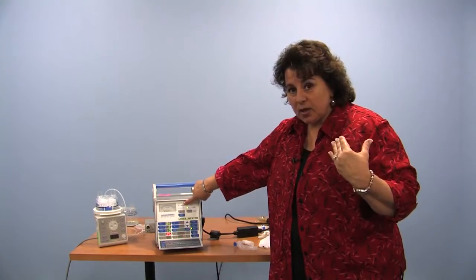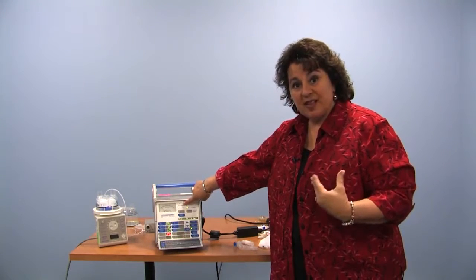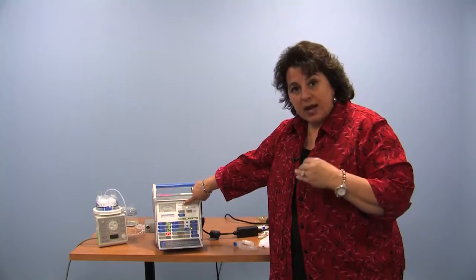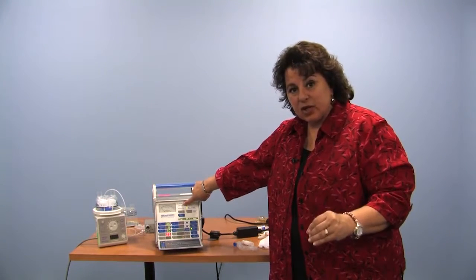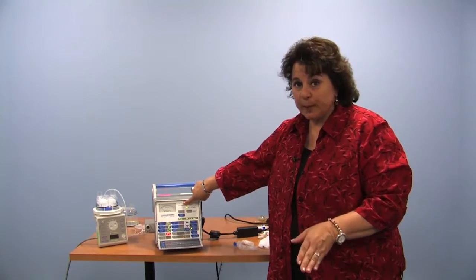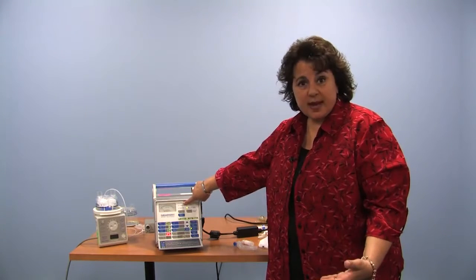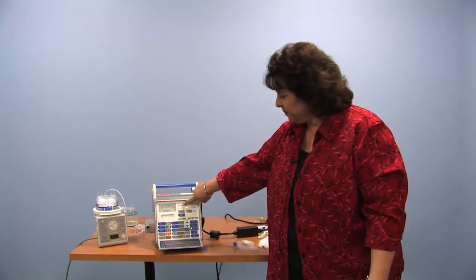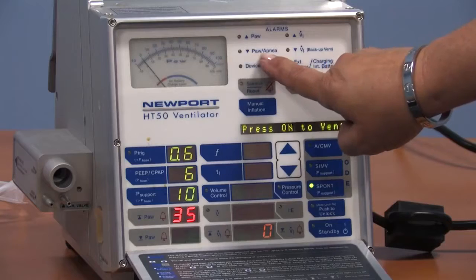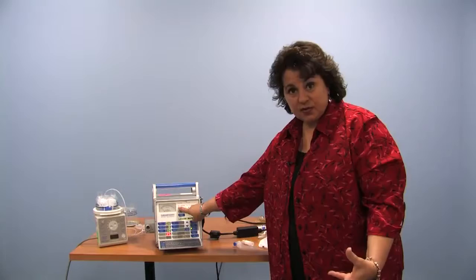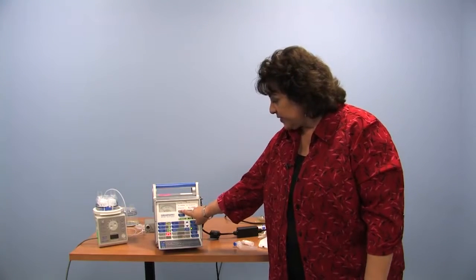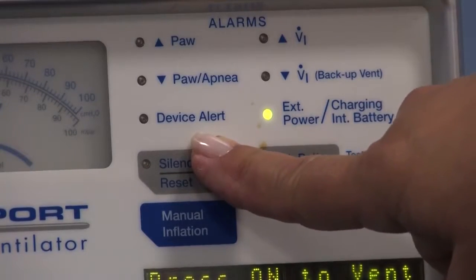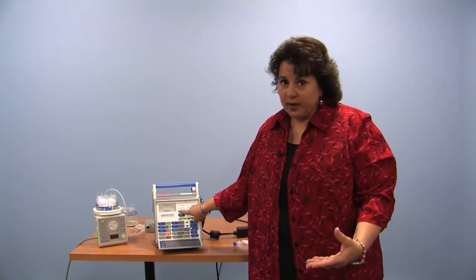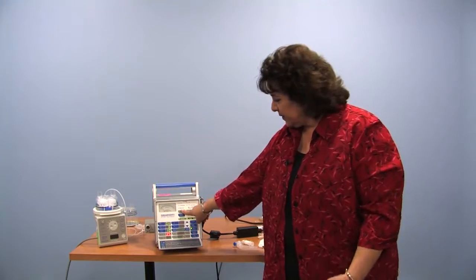There'll be an audible alarm for as long as that situation is still active. When the high pressure situation goes away, the light will remain on. So if you leave the room and come back and you heard a beep, you can see what went off, but perhaps it was reset because the child coughed once and that was all. We can see a low pressure alarm, which typically would be disconnection of the circuit. Device alert would mean that you would be taking this out of service using a hand ventilation bag or your backup ventilator if you have one, and calling the company to have it replaced.